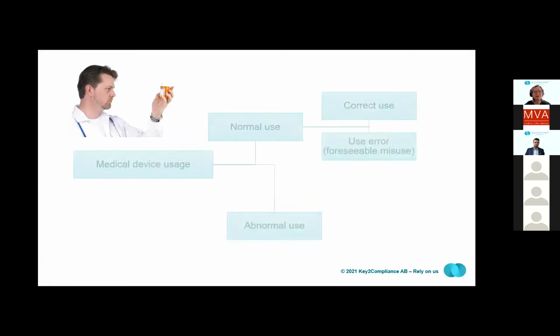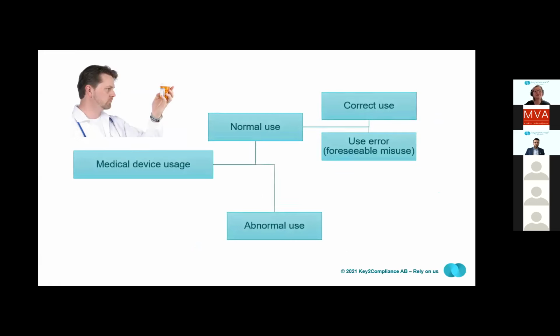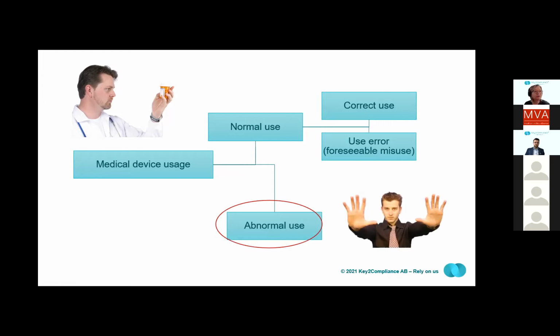Another thing that relates to this a little is that as a manufacturer, when handing over the device to the market, you must ensure that the users understand what the medical device usage is, and you must also define what the normal use is, and give instructions so that it is easy for the users and patients to use the device correctly. You must also put efforts into identifying potential use errors and foreseeable misuse. And if you become aware that the device is used outside the approved correct use, or outside what is covered in your risk analysis as use error or foreseeable misuse, it is important that people in the organization are aware that you need to react on abnormal use and communicate that this is not part of our approved intended use.